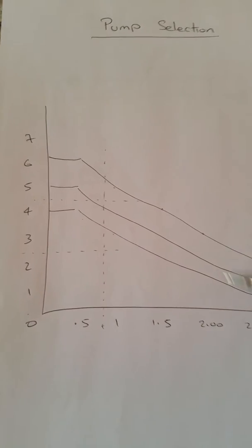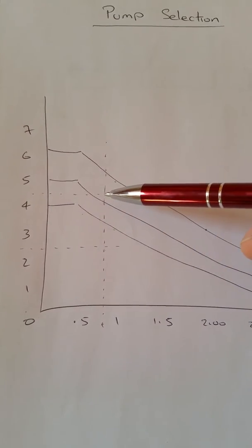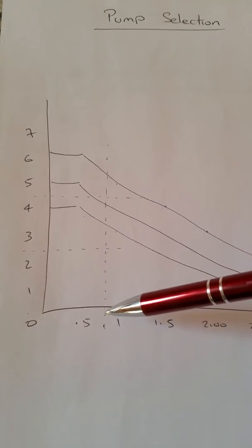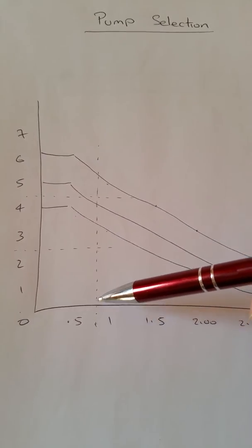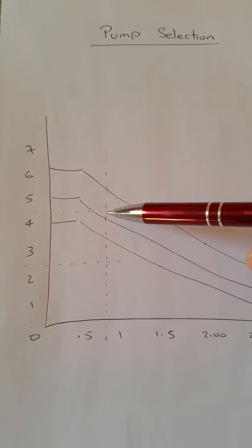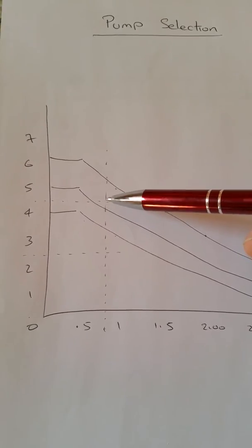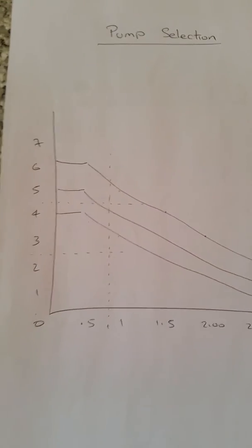There will be a second part which shows a resistance through our heat exchanger of 4.5 meters at the same flow rate, so that's 0.75 something or other cubic meters. And that's going to show that we need a 1560 pump on setting 3 in order just to overcome the resistance in the heat exchanger.